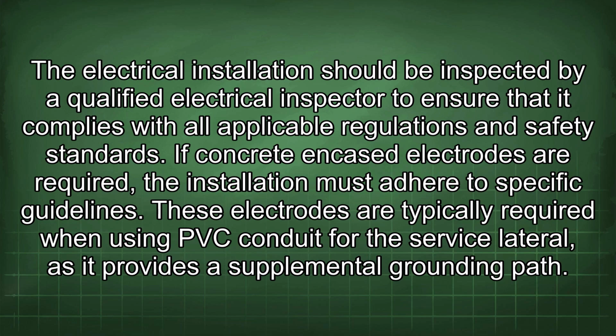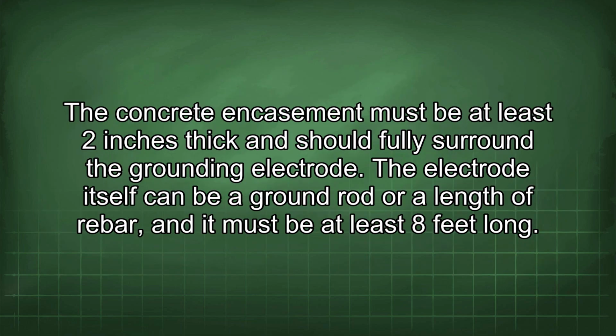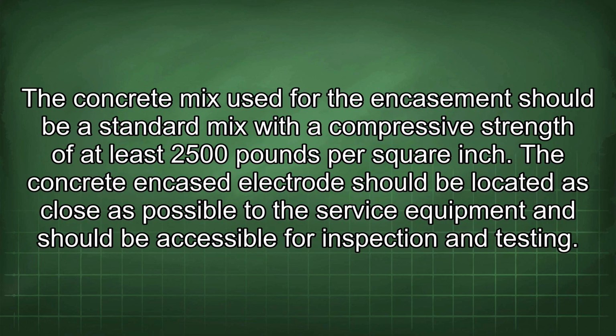If concrete encased electrodes are required, the installation must adhere to specific guidelines. These electrodes are typically required when using PVC conduit for the service lateral, as it provides a supplemental grounding path. The concrete encasement must be at least 2 inches thick and should fully surround the grounding electrode. The electrode itself can be a ground rod or a length of rebar, and it must be at least 8 feet long. The concrete mix used for the encasement should be a standard mix with a compressive strength of at least 2,500 pounds per square inch.